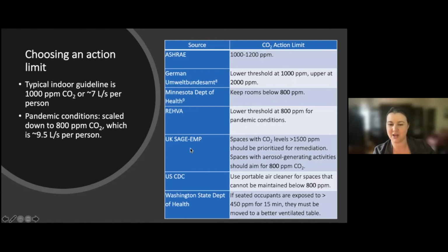This UK Scientific Advisory Group said that if you're going to be doing aerosol-generating activities—that could be medical procedures, singing, or high-intensity exercise—then you should be aiming for not exceeding 800 ppm CO2. The CDC likewise went to 800, which corresponds to a ventilation rate of about 9.5 liters per second per person.